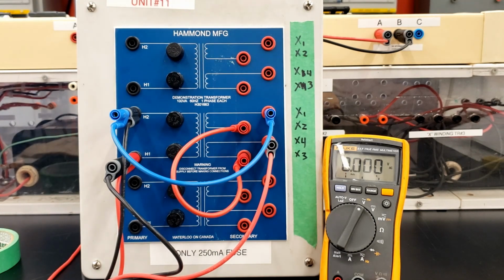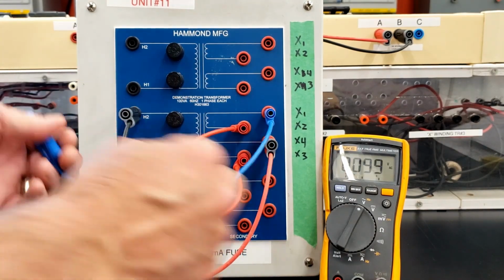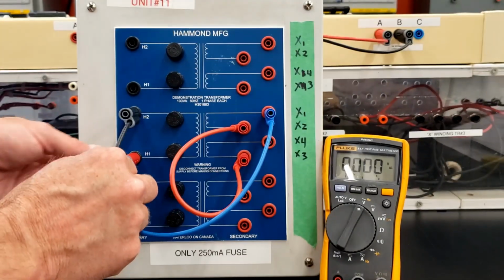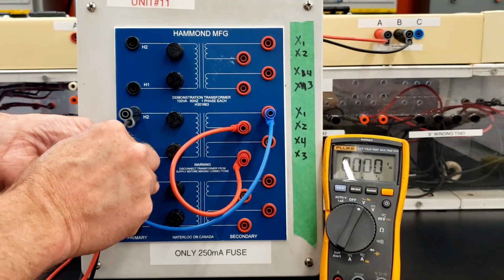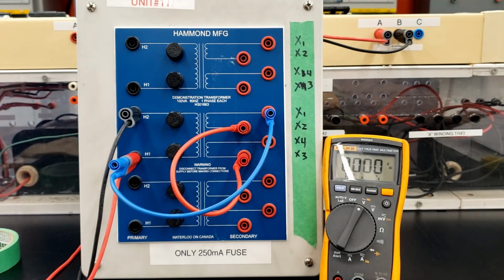Let's take a look at the subtractive voltage now. Subtractive voltage is always H1 to X1. So I'm taking the meter out of the circuit here, moving it from X1 to H2, over to H1 now, going to the opposite connection of the primary winding.